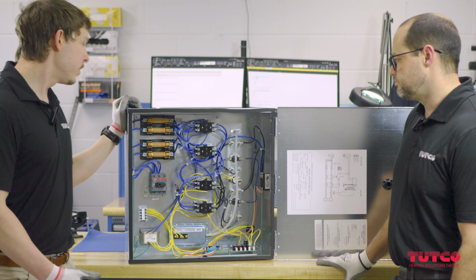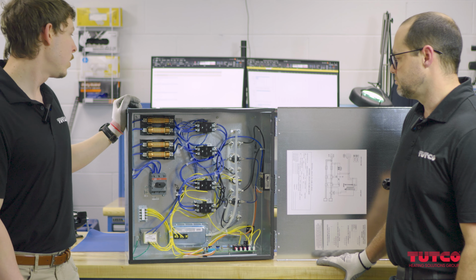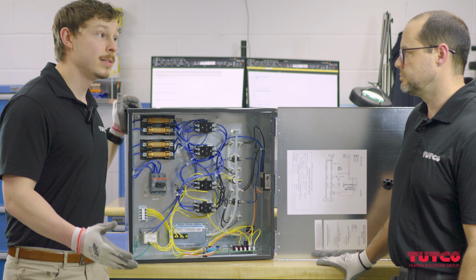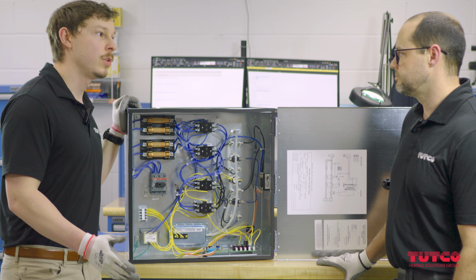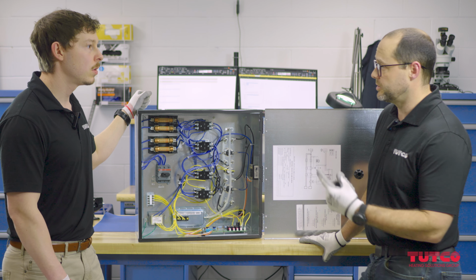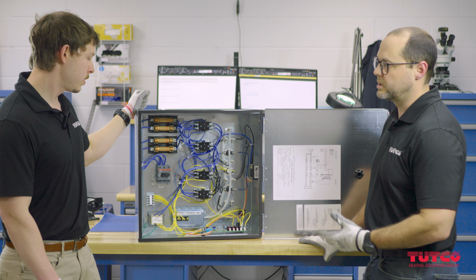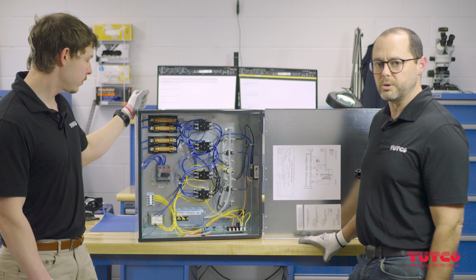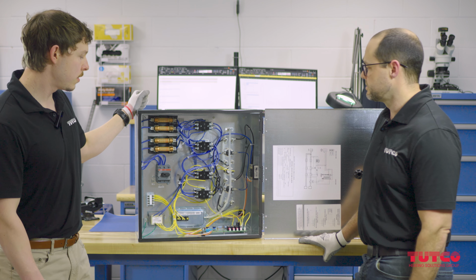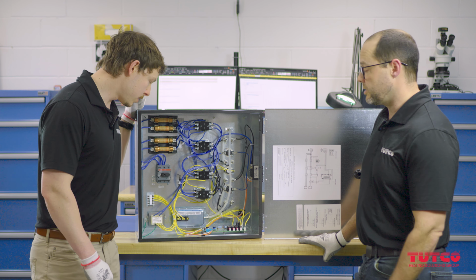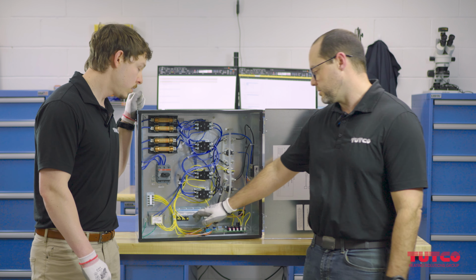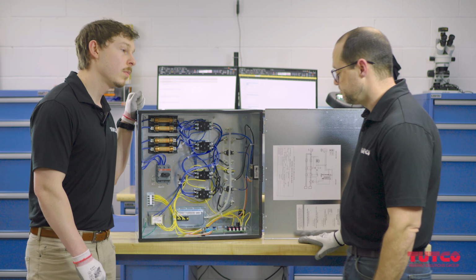I've been noticing it takes a while for my air to actually reach my duct heater, since it's kind of far off from the central unit. We offer a time delay for that, so the heater elements don't kick on before the fan is able to get up to speed and provide enough air. We also offer a fan relay in place of an airflow switch.